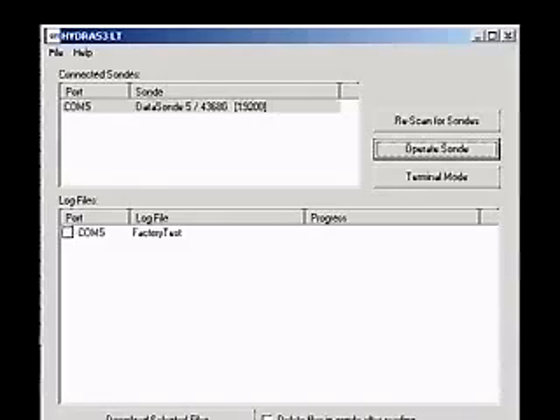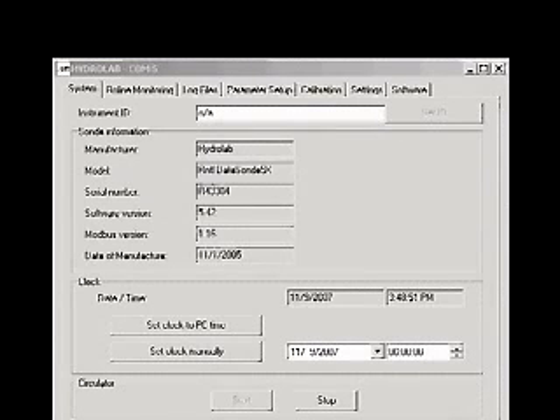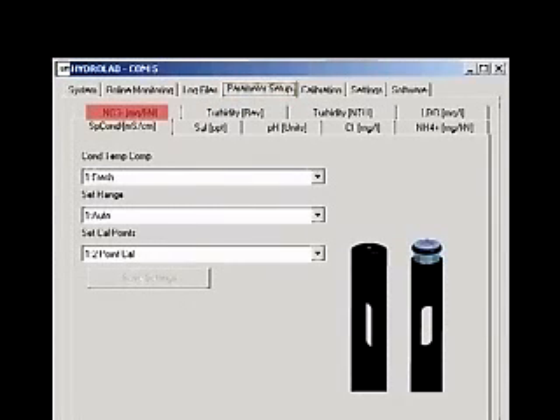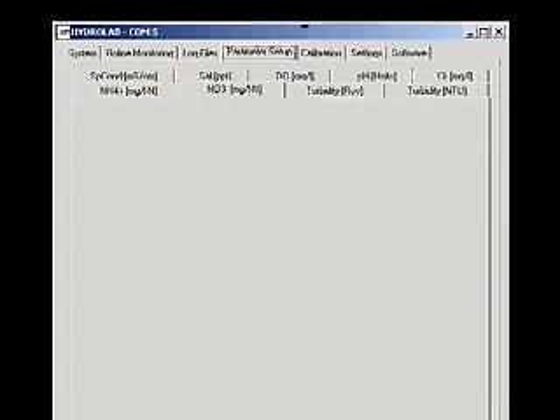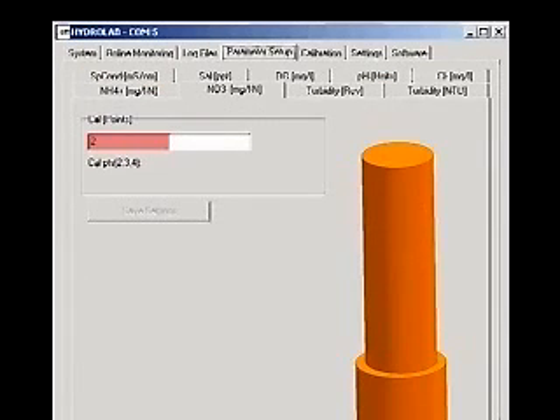Establish a connection to the Sonde with Hydras 3LT. Click the button labeled Operate Sonde. When the Sonde finishes its initialization, click the Parameter Setup tab. Then click the Ion Milligrams per Liter tab. Type the number of calibration points you are using in the box and click Save Settings.